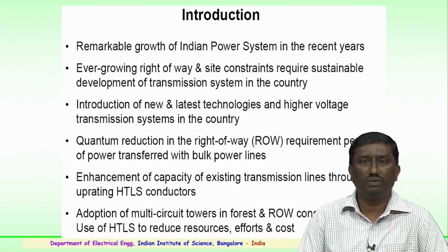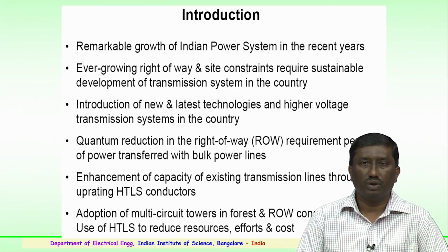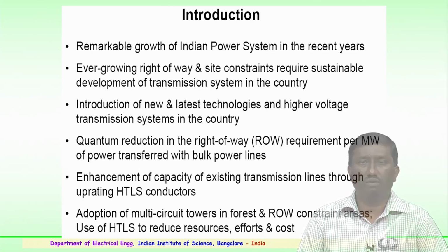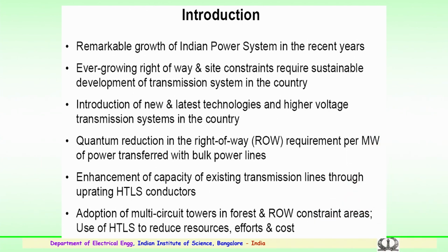With the introduction of new and latest technologies for higher voltage transmission systems in the country, there is a quantum reduction in the newer towers which have been designed, particularly the right of way has been reduced, and so has the requirement per megawatt of power transferred with bulk power transmission lines operating at very high and ultra high voltage. The enhancement of the capacity of existing transmission lines could be done by uprating, using newer types of conductors, that is the high temperature low sag conductors, which we briefly discussed, for the uprating or upgradation of existing transmission lines.